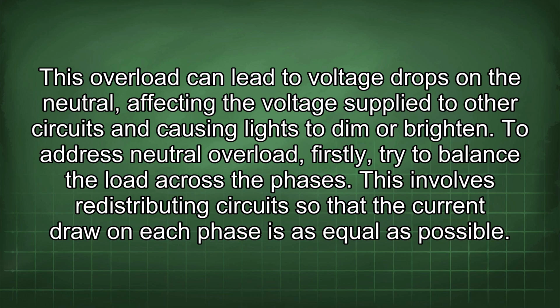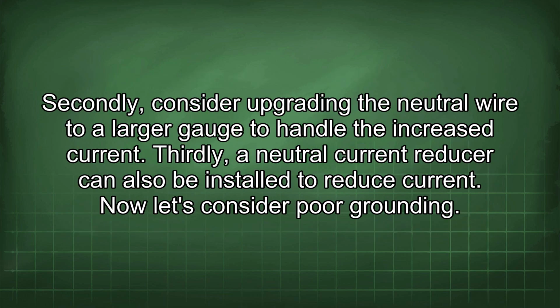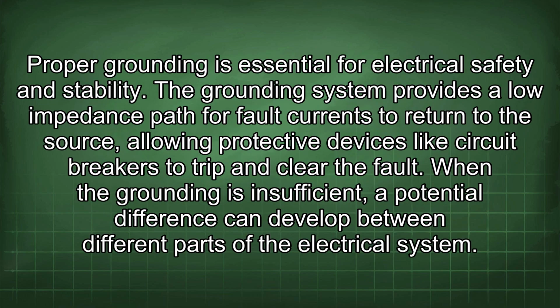This involves redistributing circuits so that the current draw on each phase is as equal as possible. Secondly, consider upgrading the neutral wire to a larger gauge to handle the increased current. Thirdly, a neutral current reducer can also be installed to reduce current. Now let's consider poor grounding. Proper grounding is essential for electrical safety and stability.